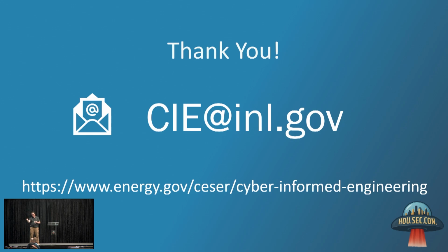And that's where we came in with that $10 time delay relay off that output channel, so that no matter how quickly that relay card was being cycled, the effect of it never translated to the pump, because the command was held in place for 10 minutes, 20 minutes within the plant dynamics, so that the pump never experienced that cycling. Our modeling proved that if we cycled anything less than 600 milliseconds, the inrush current would burn out the pump because there was no time to dissipate that heat. So that's where we retrofitted in a time delay relay off that output channel to control that effect before it hit the contactor. That's one example.